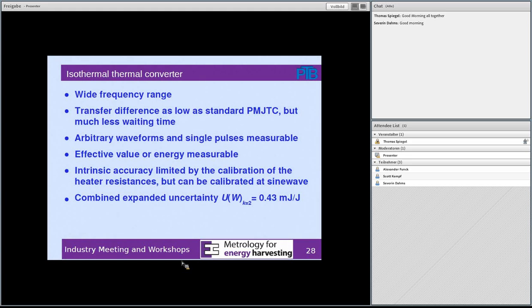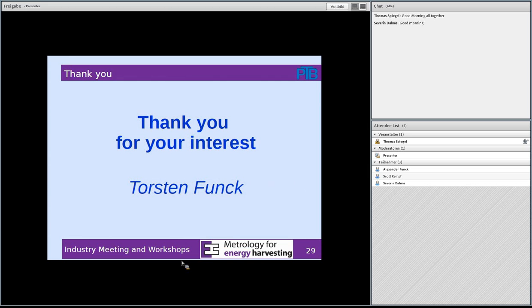You may consider situations where an effective value is not really useful, that it's better to say, okay, in this 10 seconds we had this amount of energy. Intrinsic accuracy is limited by the calibration of heater resistances, but you can always use a sine wave to calibrate it, or you can even use DC to calibrate it. And the combined uncertainty is about 0.4, 0.5 millijoules per joule. So, thank you for your interest and questions.